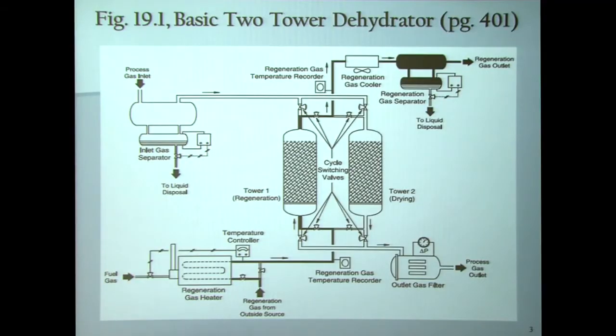In today's discussion, we are simply going to focus on a process flow diagram, and I will take you through the major steps. What we have over here is a simplified PFD of a system using adsorbents, particularly molecular sieves, to dehydrate a natural gas stream. Molecular sieves are used when you want to get your product gas to very low water concentrations, less than a tenth of a part per million by volume, which is often needed if you're feeding a turbo expander plant or an LNG plant.